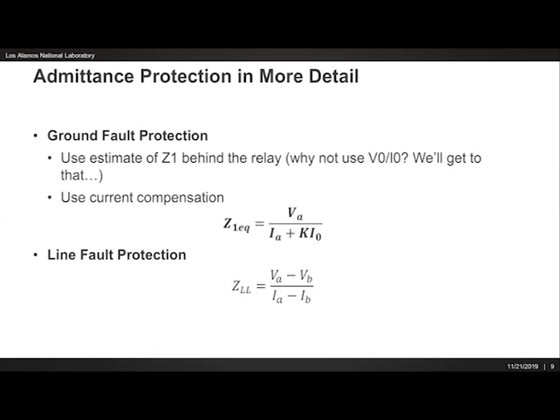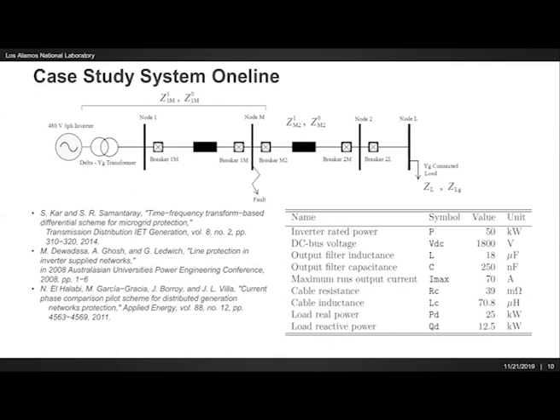And this is beneficial because of the question that I'm asking in this first bullet point, which is the ratio of positive negative sequence voltage to current. And we'll see in the following slide that this first quantity will actually give us a distance to the source or a generator as opposed to the fault. So that will completely screw up protection coordination.